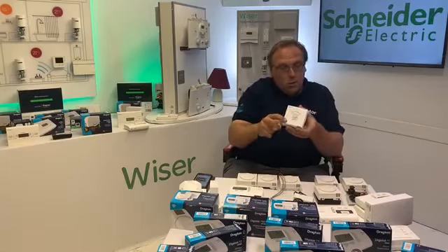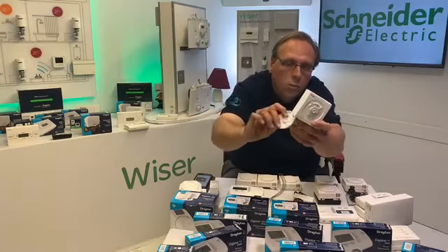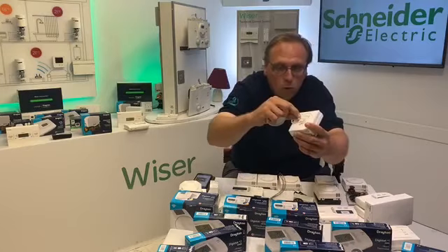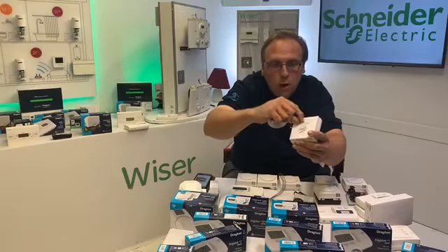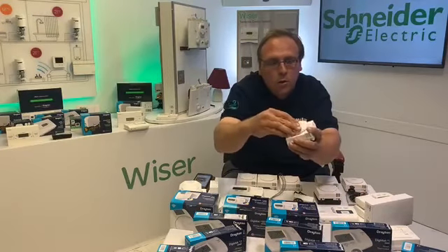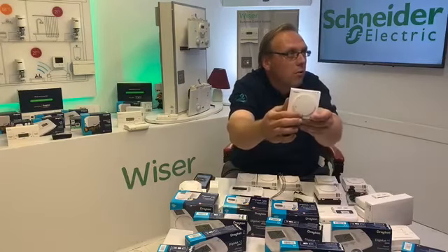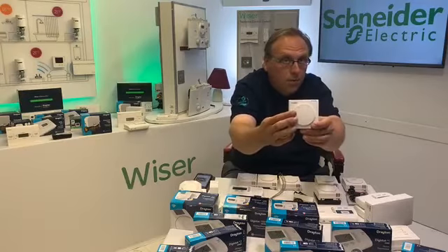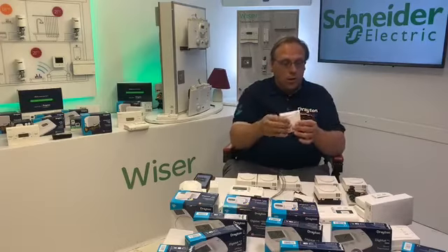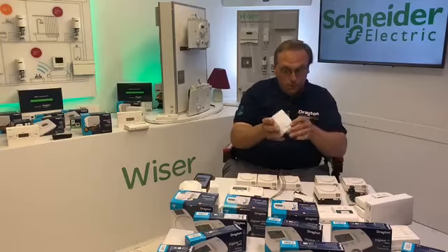Underneath the cap, you've got these arms which allow you to range limit. These coincide with, on the back of the dial, a little nodule there. If you want to range limit, you can move the arms around, and then depending on where you put the dial when you put it back on, with respect to where those arms are, you can range limit. You can see now that I'm limiting it on the upper side, so you can do a high limit, a low limit, or you can do a range in between. That's quite nice, and obviously with the dial on, nobody knows it's there, so it's quite good if you want to do range limiting.